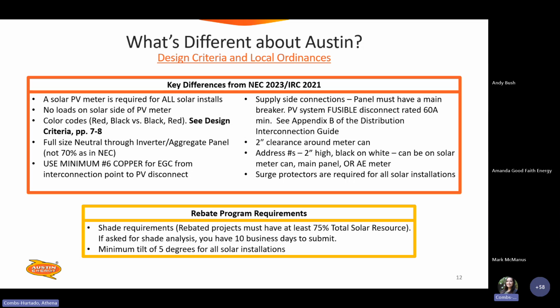All right, so what is different about Austin? The design criteria and local ordinance. So the key differences from NEC 2023, IRC 2021. A solar permit or a solar PV meter must be required for all solar installs. No loads on solar side of PV meter. Color codes, please make sure to see the design criteria manual, pages 7 and 8.